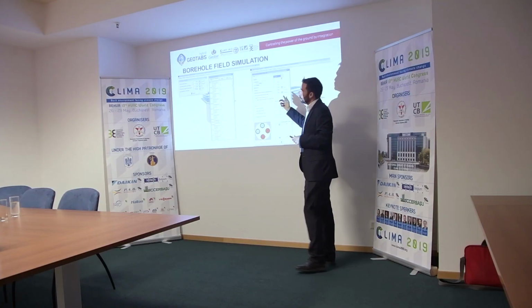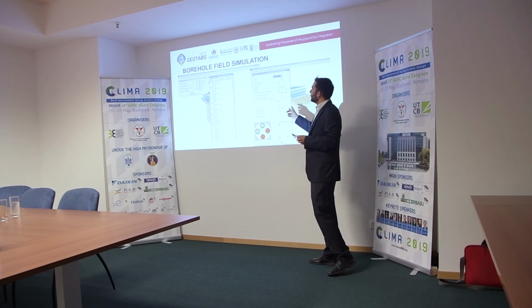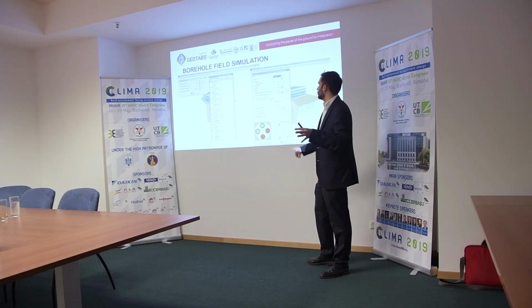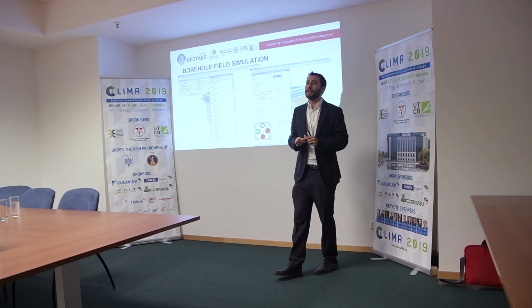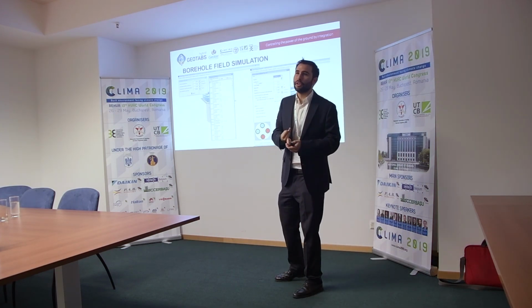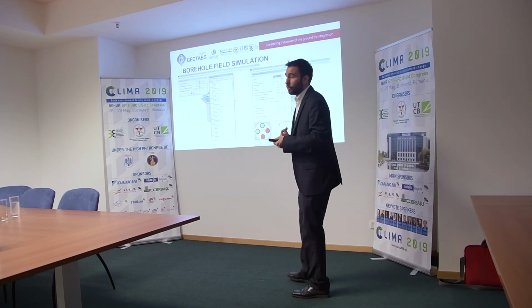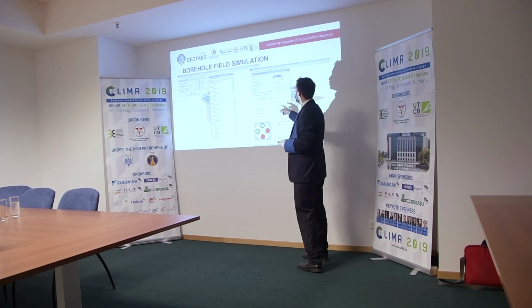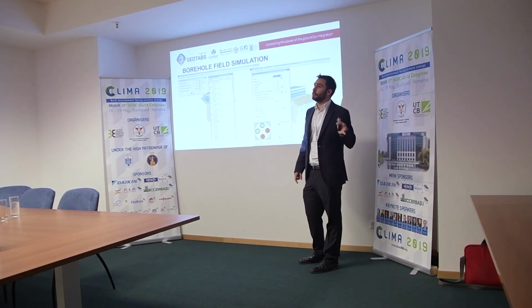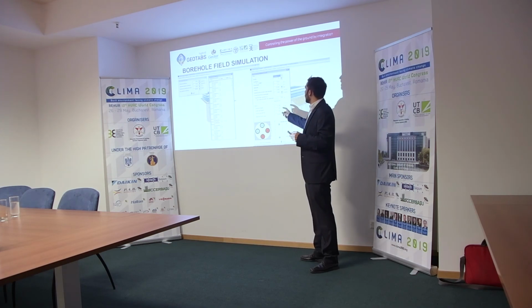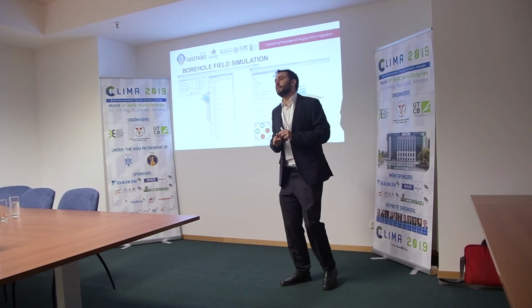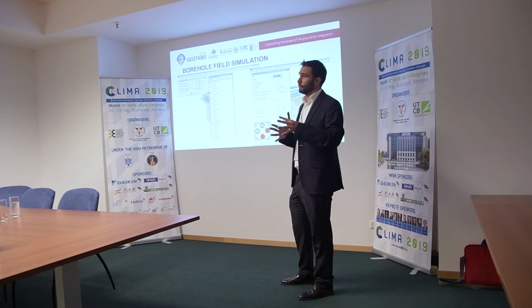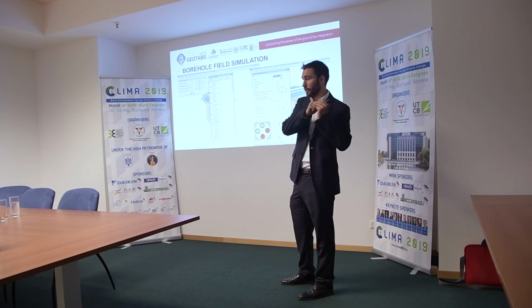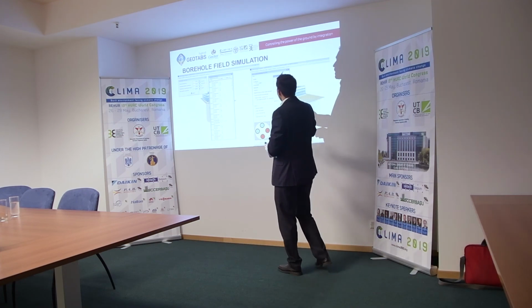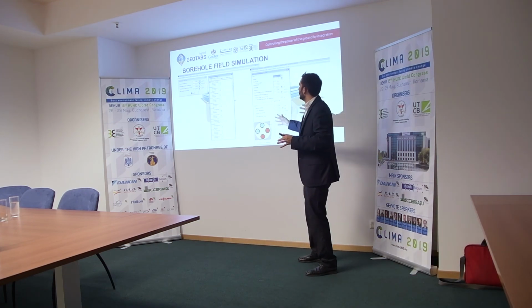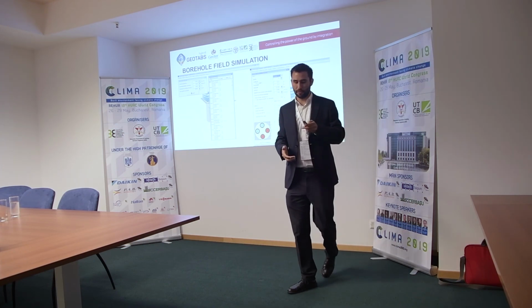In a second stage, you have to introduce different features about your geothermal installation. You have to choose if you are going to use simple U, double U configuration or a coaxial geothermal probe, for example. You have to introduce the thermal conductivity of the mortar. Here you can introduce the delta T of the geothermal heat pump at the evaporator side. And here you can introduce a little pre-sizing of your installation. Okay?